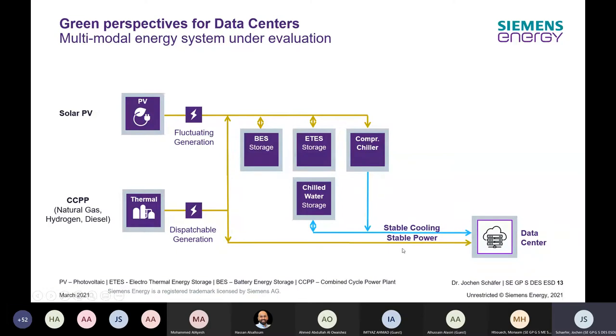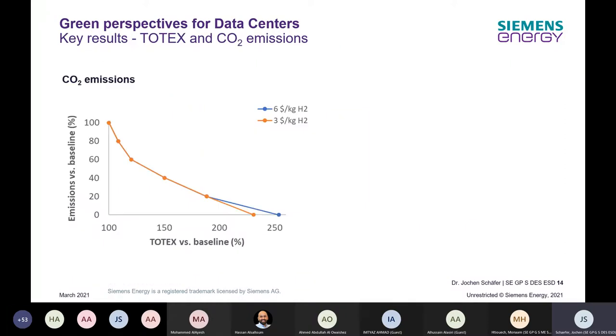Electricity comes from the combined cycle plant in a reliable manner, and we operate a compression chiller to supply cooling. To decarbonize, we include renewable energy — specifically PV — which creates fluctuating generation. We balance these fluctuations using a battery energy storage and/or an electrothermal energy storage, plus a chilled water storage to decouple cooling from the compression chiller's electrical power draw — a third form of flexibility. Now let's look at the associated costs.